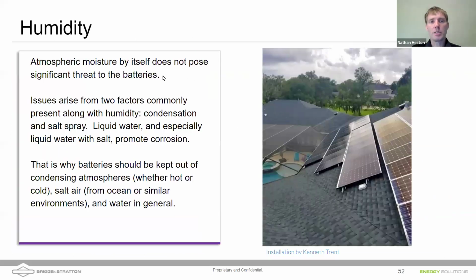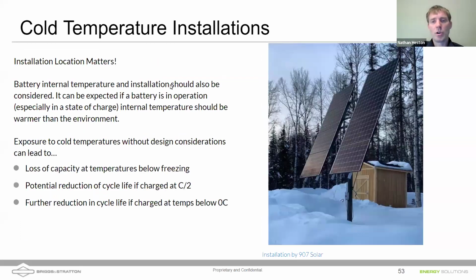I just want to point out that atmospheric humidity by itself doesn't pose a threat to the batteries, but if you're in high salt areas, you would want to keep these batteries, especially out of a direct exposure to salt water that could be in the air, for instance. So keeping them inside a NEMA 3R enclosure is a good idea. It prevents that salt condensation on the batteries, which can cause corrosion. For cold temperature installation, it is a good idea to keep your batteries inside an insulated enclosure if possible, and potentially even offer some heat. You might get more usable capacity out of your batteries if you use some of the energy in the batteries to keep them warm.